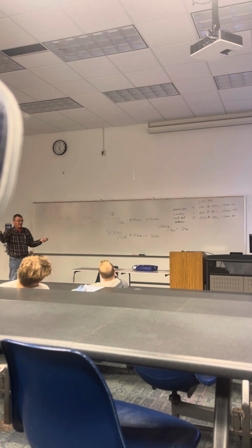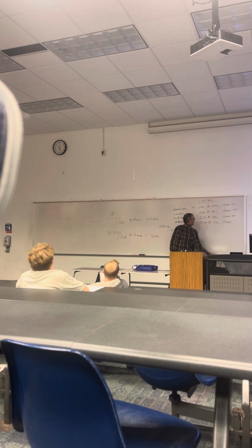If you just put receptacles in the bathroom on that circuit, you can put both of them on it. But your vanity light you can't have on it. So you might better put 2 20 amp at 120 volts. That's 12 AWG, 12 gauge NM. There's 2 more spots in your panel.